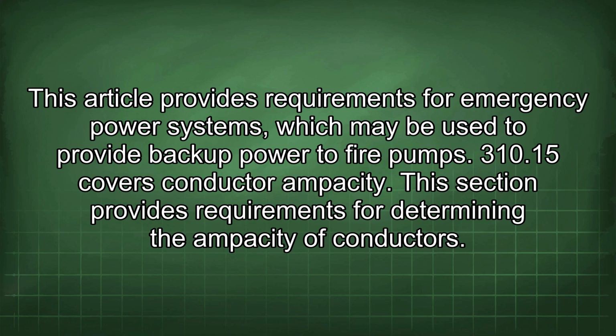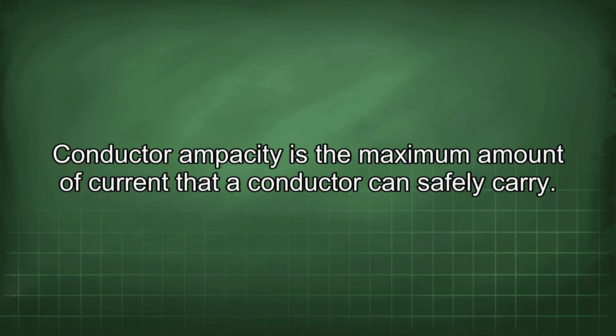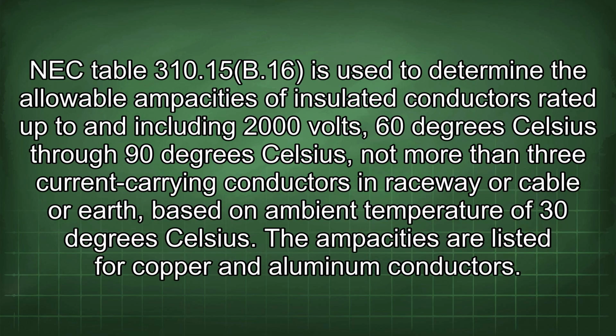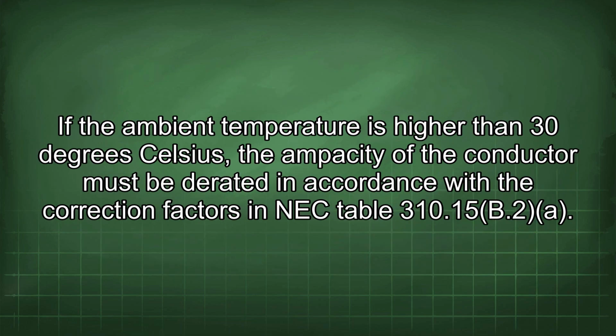310.15 covers conductor ampacity. This section provides requirements for determining the ampacity of conductors. Conductor ampacity is the maximum amount of current that a conductor can safely carry. NEC Table 310.15(B)(16) is used to determine the allowable ampacities of insulated conductors rated up to and including 2000 volts, 60 degrees Celsius through 90 degrees Celsius, not more than 3 current carrying conductors in raceway or cable or earth, based on ambient temperature of 30 degrees Celsius. The ampacities are listed for copper and aluminum conductors. If the ambient temperature is higher than 30 degrees Celsius, the ampacity of the conductor must be derated in accordance with the correction factors in NEC Table 310.15(B)(2).